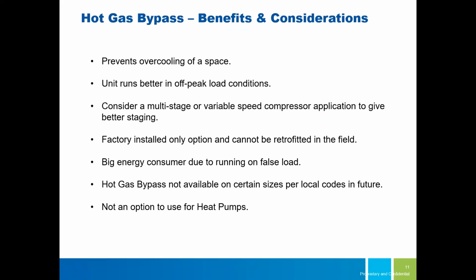If you're in a situation like this, you're never going to overcool the space, right? And this also keeps your unit running better in off-peak load conditions. Now, I would say here as a former consulting engineer of 20 years that hot gas bypass, yes, is something you can do to avoid a situation like the church job we just talked about. But think of it kind of like a Band-Aid, because in reality, as a consulting engineer, you should also be paying attention to the fact that 10 tons is what I need when all 300 people are in that room, and 2 tons is what happens when nobody is there.